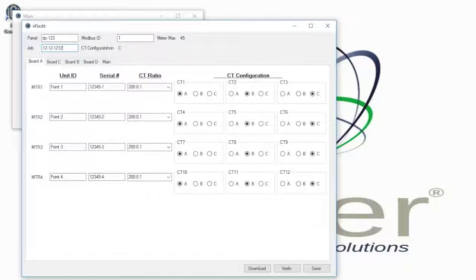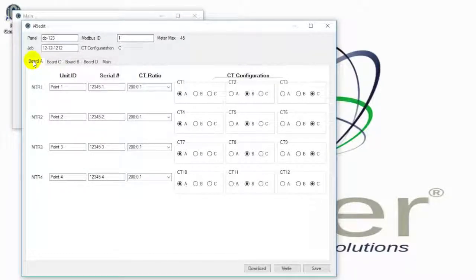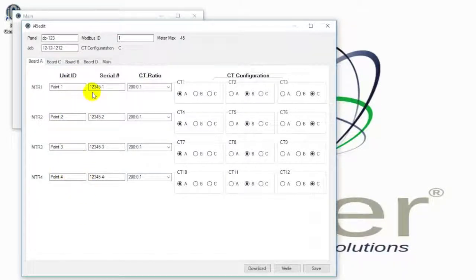The first column on the left is the meter number, which will incrementally add up to the maximum number of metering points depending on the configuration. The next column is unit ID, a generic auto-fill naming convention that can be adjusted up to a maximum of 15 characters. The next column is the serial number, a combination of the meter number and the actual serial number entered on the main screen — this can be adjusted but must have a unique ID. The CT ratio column replicates the ratio of CT being used in the panel at each metering point, and can be adjusted if the CT ratio differs from what was selected on the main screen.